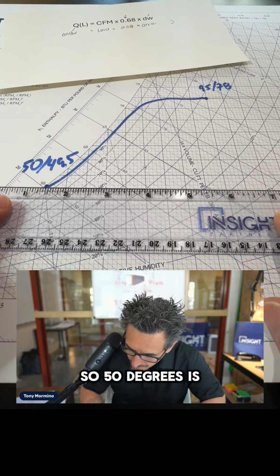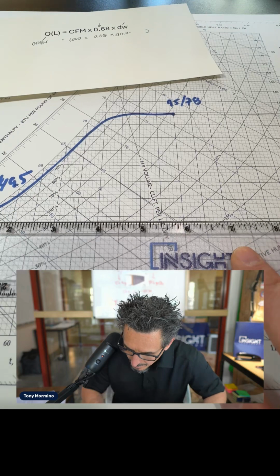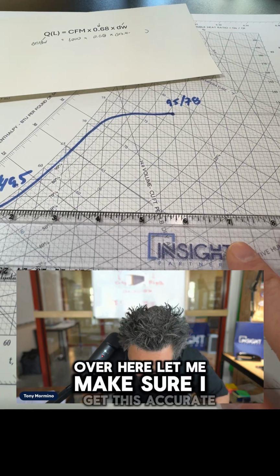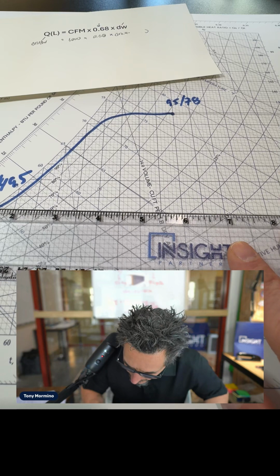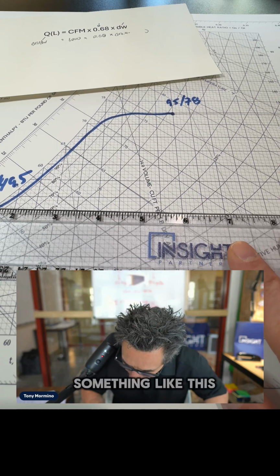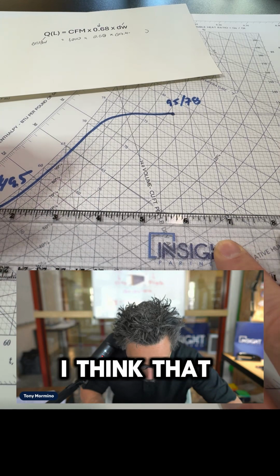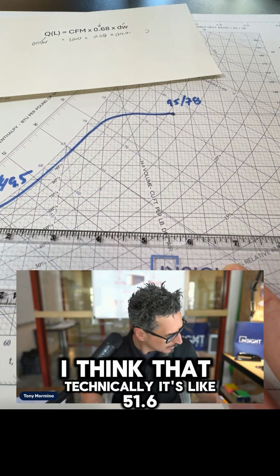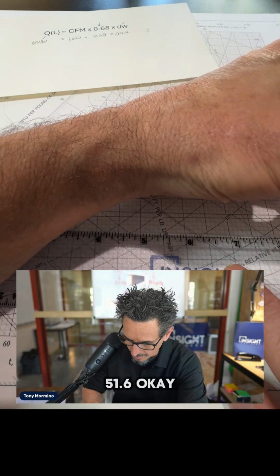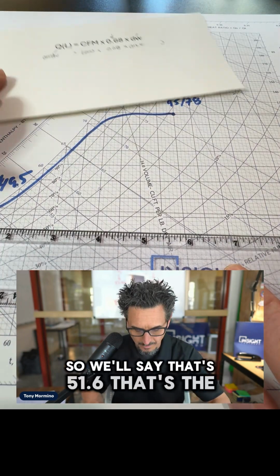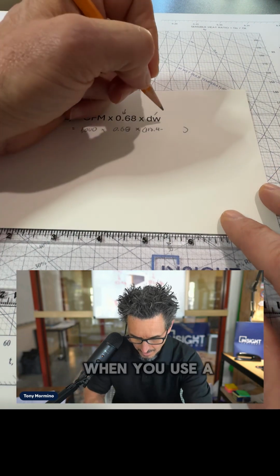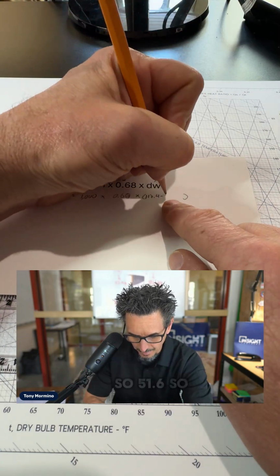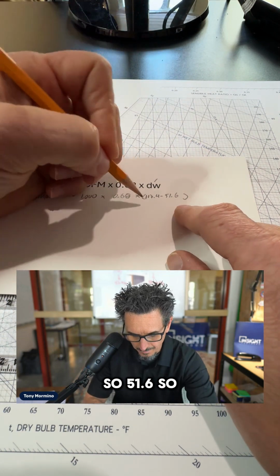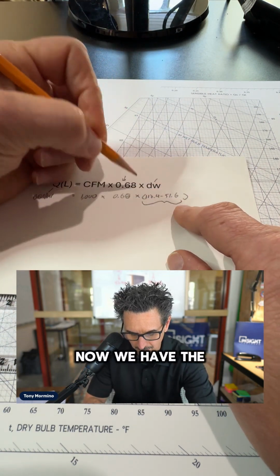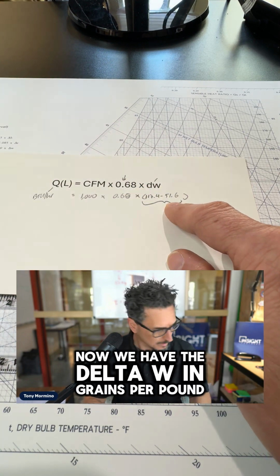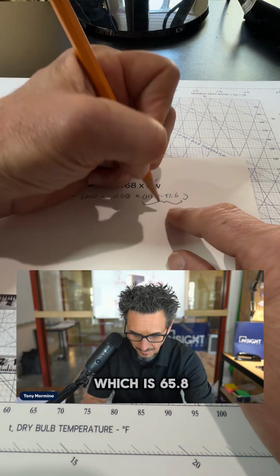Minus the grains at the lower conditions. So 50 degrees is something like over here. Let me make sure I get this accurate. Something like this. I think that technically it's like 51.6. Okay, so we'll say that's 51.6. That's the accurate value when you use an app to calculate it. So now we have the delta W in grains per pound of dry air, which is 65.8.